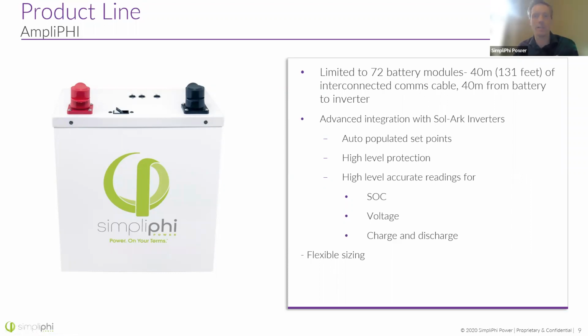This easily integrates with Sol-Ark inverters. In fact, we sell Sol-Ark inverters as part of a product ESS. They auto-populate the set points and have high levels of protection and accurate readings in terms of state of charge, voltage, charge and discharge, and temperature. There's even temperature control for charging slowly below 0 degrees Celsius.